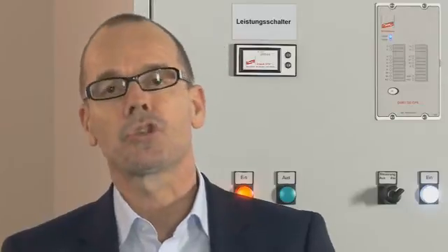The causes for the formation of arc faults in low voltage switchgear installations can be classified into two categories. Firstly, internal faults in the switchgear installation caused by faulty contact points, failure of electrical equipment, or pollution and aging.